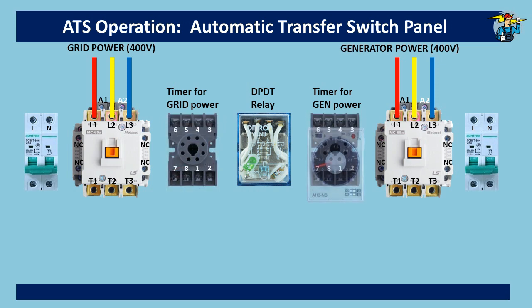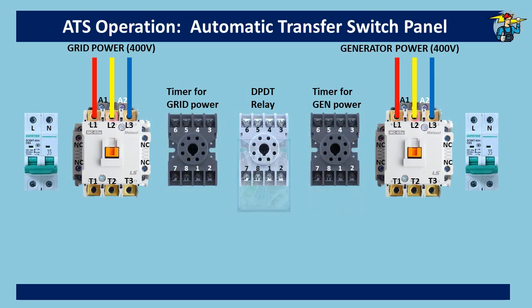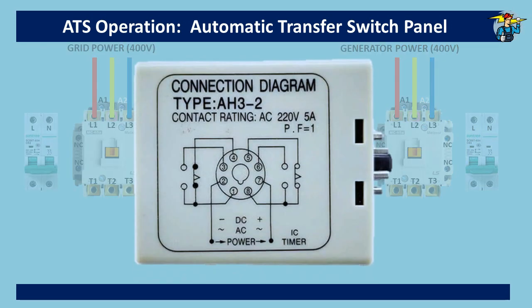When you take timers and relay out of their bases, you will see numbered ports. This picture shows how the positions are numbered for the normally open and normally closed positions, the common points, and the power supply points. Power connection for the relay or timer is given through points 2 and 7.